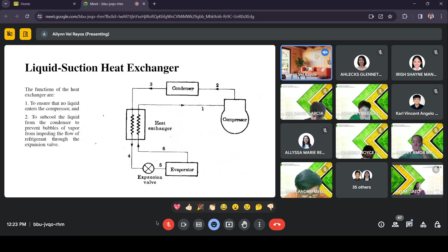Here, what was removed is sensible heat, because heat is rejected with a change in temperature, but it's still liquid throughout. At point 3 it's already liquid, and for subcooling it's still liquid, but there is a decrease in temperature from 36 to 30 degrees Celsius.